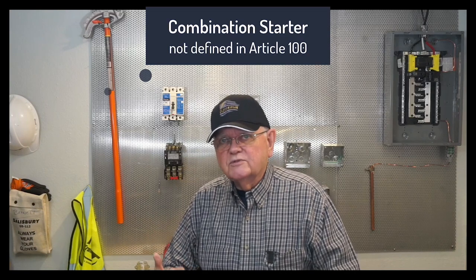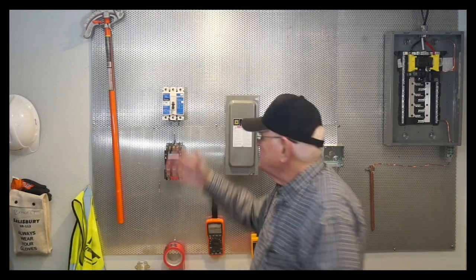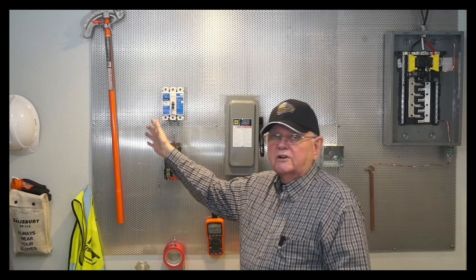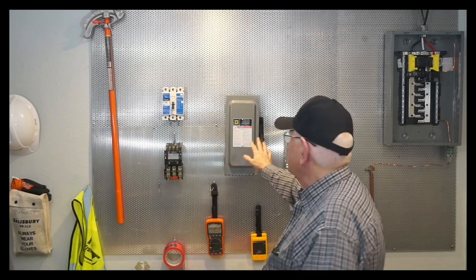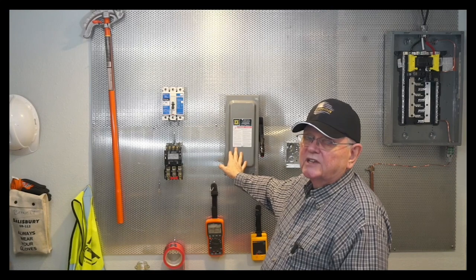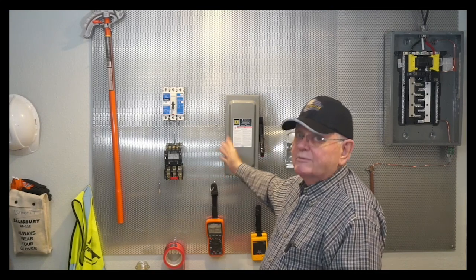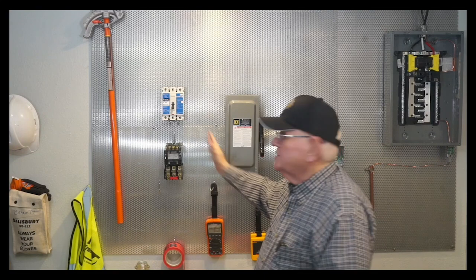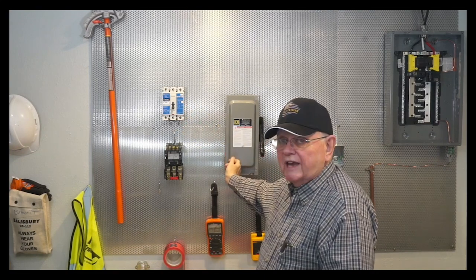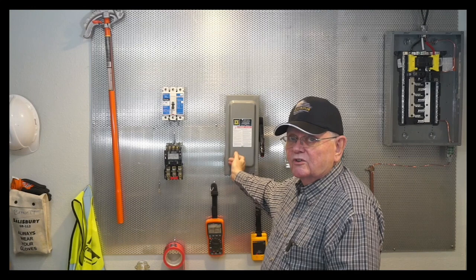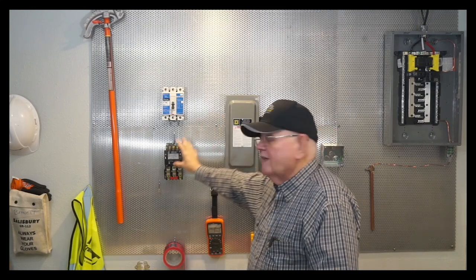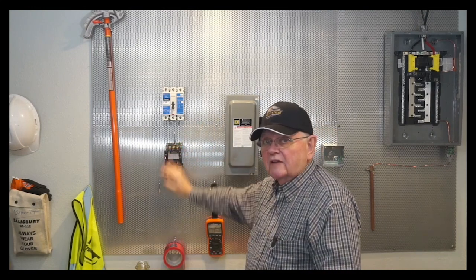But there are different types of combination starters. You may see something like this inside of a motor control center. You may see a similar arrangement inside of what looks like a disconnect switch, larger than this one, but it'll be a fuse disconnect. So instead of a circuit breaker, I have a fuse disconnect. The fuses supply my short circuit and ground fault protection, and then I have my entire motor starter with my contacts and my overload protection in it anyway. So just a little clarification maybe on that concept. That term combination starter always seems to be a little confusing.